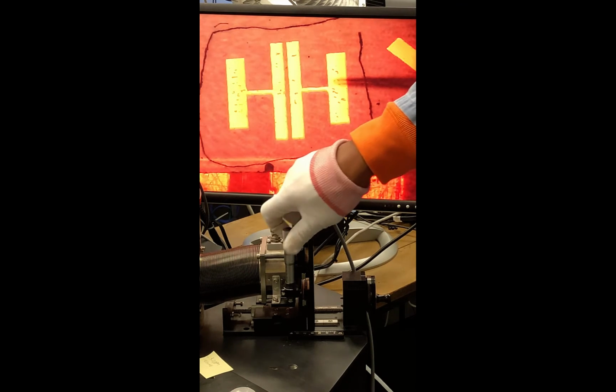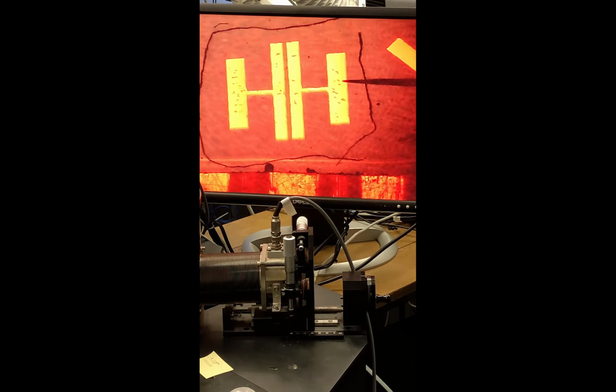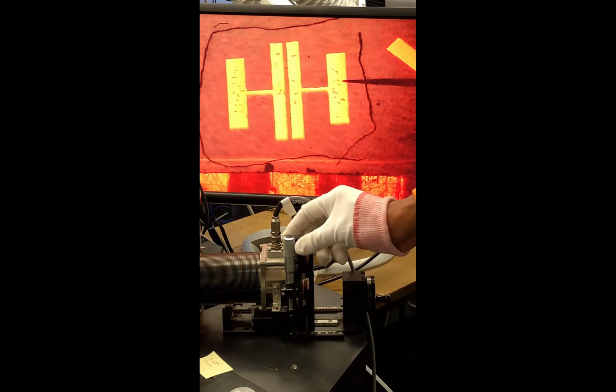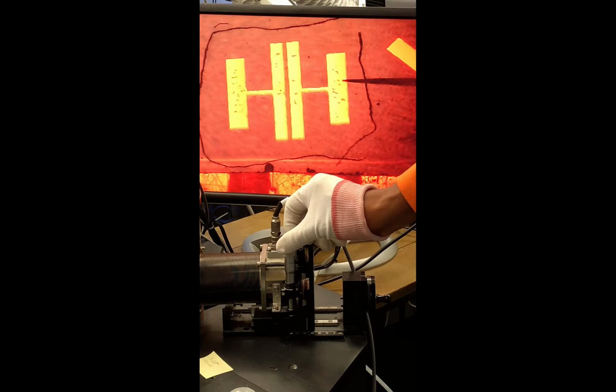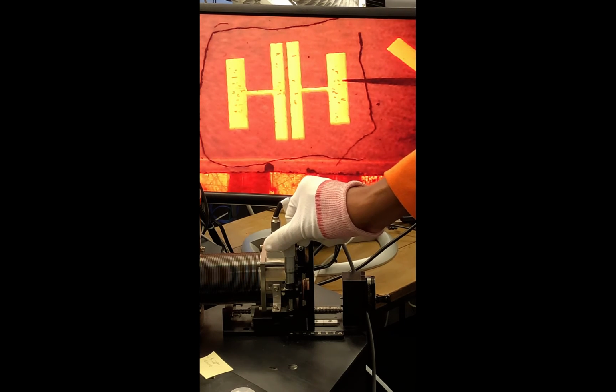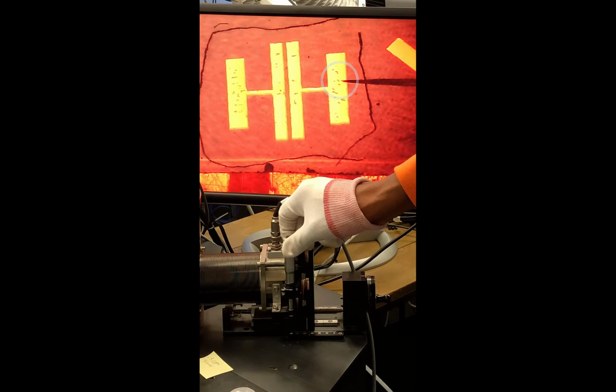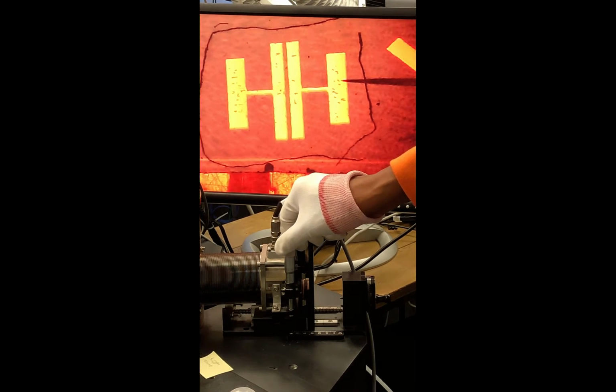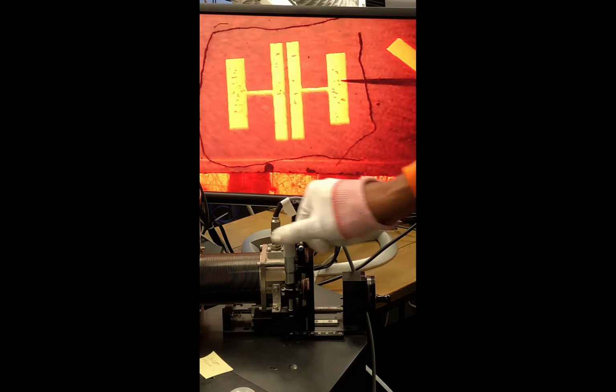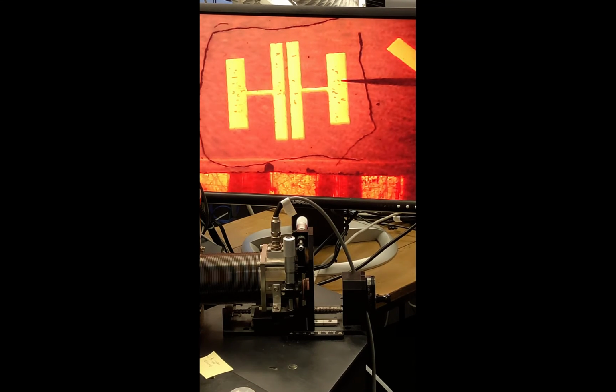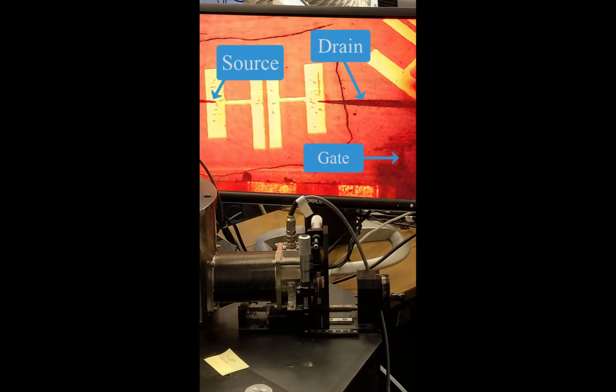It can be a little harder to see when the probe tip is in position vertically, so here's a suggestion. You'll notice that the probe tip appears to be more focused as it moves vertically until it finally reaches the sample. Then it'll move horizontally across the sample surface. You've gone just a little too far, but you know you've made contact, so you can back up a little if you like. Your first probe is in position. You may decide to test it this way, or you might also cover a light-sensitive sample with aluminum foil.